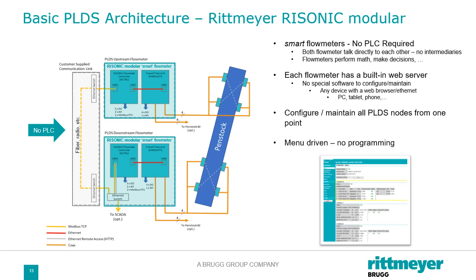And finally, everything is menu driven. There is no special programming for this. To set up the COM link, one flow meter will set up a remote input from the one flow meter to the other by going to the menu and entering the IP address of the other flow meter and which register we want to read, the one that contains the flow. And now it will continually update the flow so that the one flow meter has flow for both flow meters as if they were both resident.